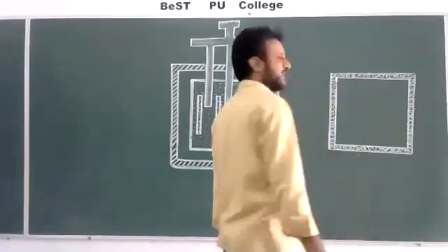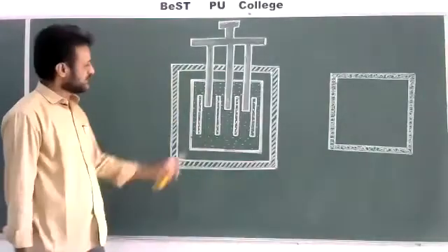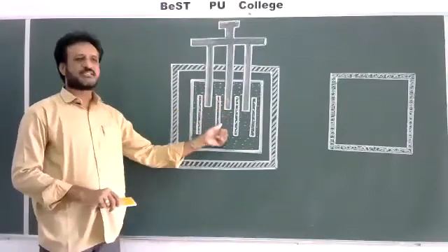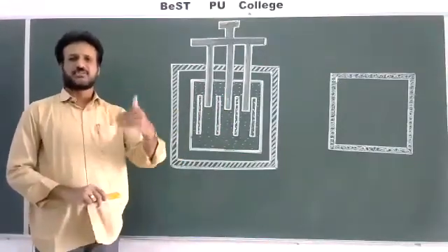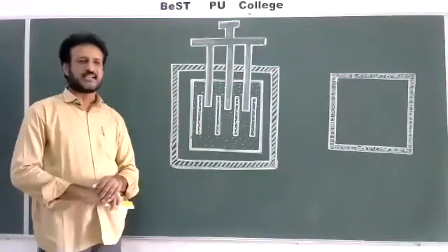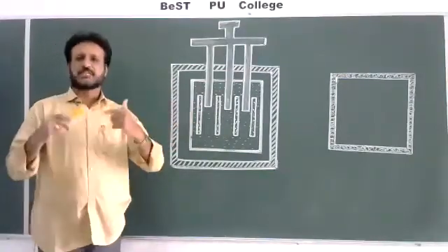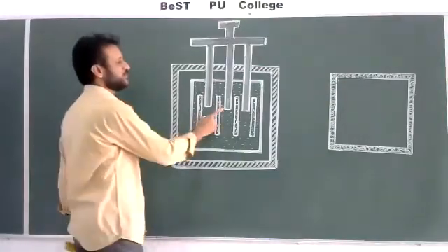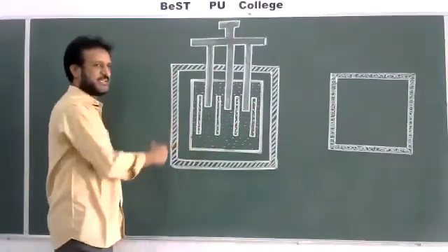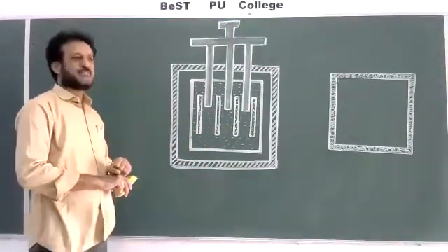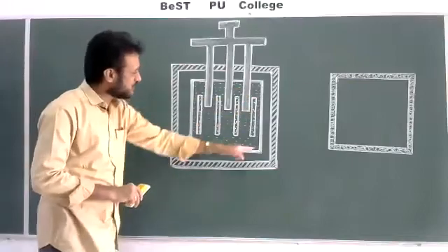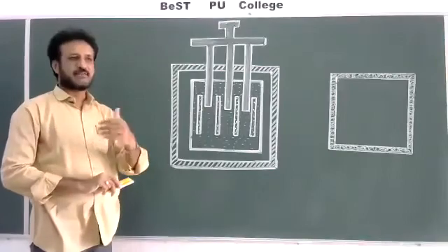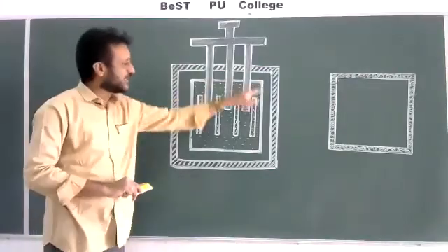And one more thing is also there inside the core of the reactor. In the nuclear fission process, a large number of neutrons are liberated. First 3 neutrons, then 9, 27 and so on. But these neutrons should again and again participate in the reaction so that energy is liberated. The fast neutrons move towards the walls of the reactor first. That's why they should be reflected back. For this, the total core of the reactor is coated with neutron reflecting materials like beryllium or graphite, and they are called neutron reflectors.